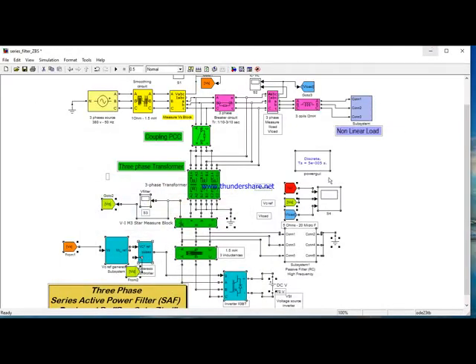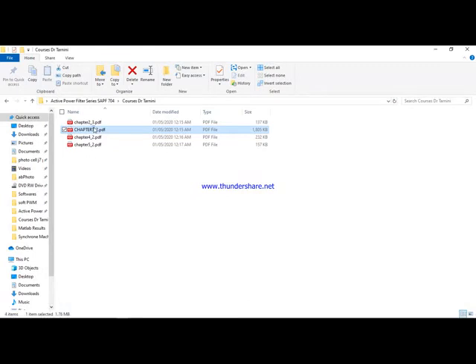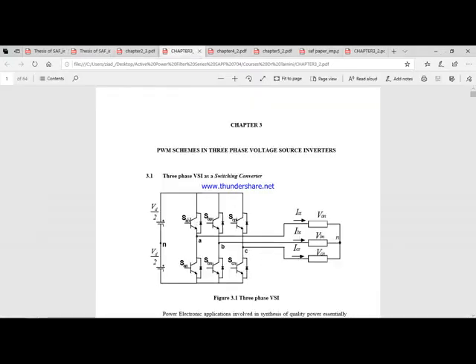When we have a difference between VC reference and VC, I want to command the gate of the IGBT converter. I have 6 IGBTs — for each phase I have 2 IGBTs. When there is a difference between VC and VC reference, I command the gate of the IGBT to generate a signal to compensate the perturbation of the main circuit.